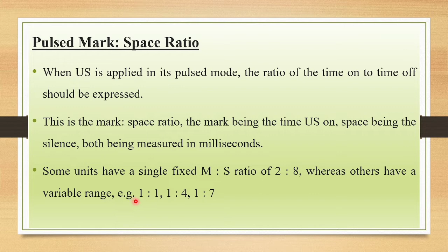Some units have a single fixed mark space ratio of 2:8, whereas others have a variable range. For example, 1:1, that is 1 millisecond on, 1 millisecond off, or 1:4, that is 1 millisecond on, 4 milliseconds off, or 1:7, 1 millisecond on, 7 milliseconds off. So it varies according to the machines.